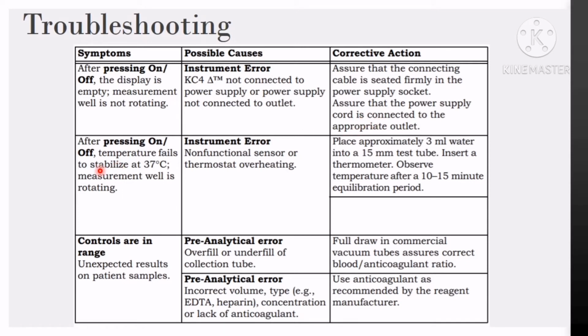Number 2 is after pressing on and off, the temperature fails to stabilize at 37 Celsius and the measurement well is rotating. This is an instrument error, where a non-functional sensor or thermostat is overheated. What you can do for the corrective action is place approximately 3 ml of water into a 15 mm test tube. Insert a thermometer, and observe the temperature after a 10 to 15 minute equilibration period.